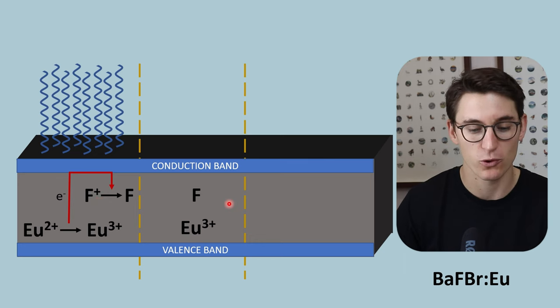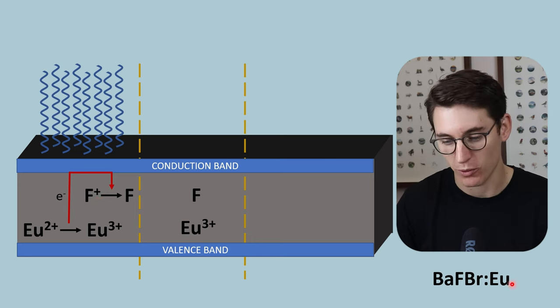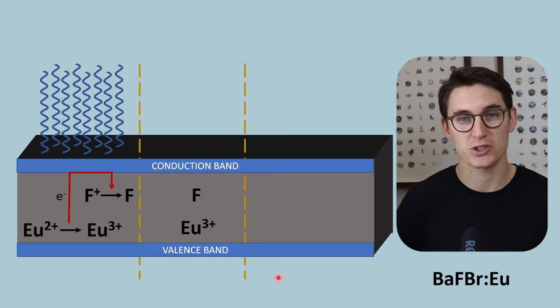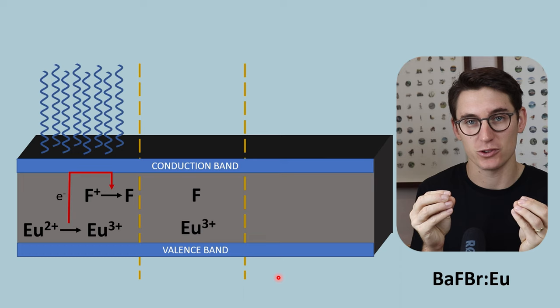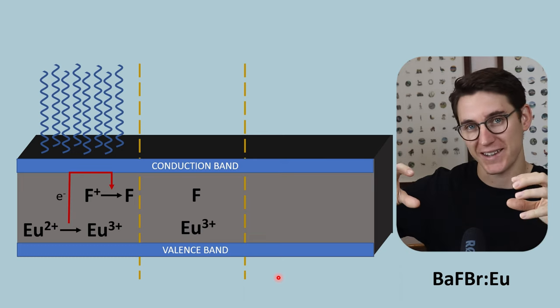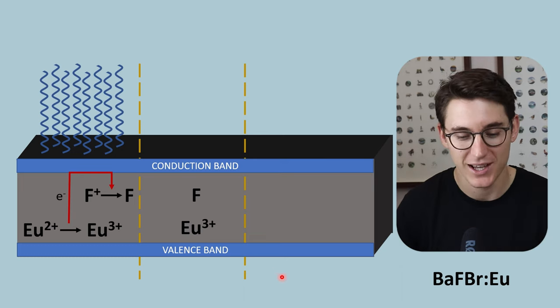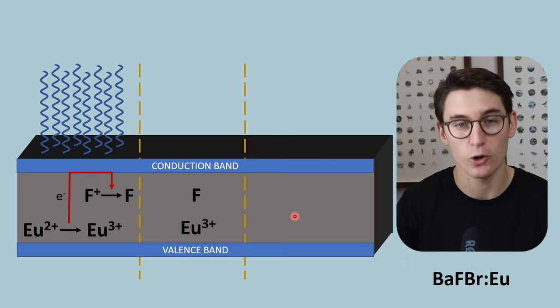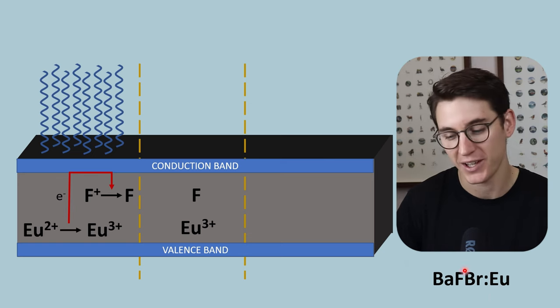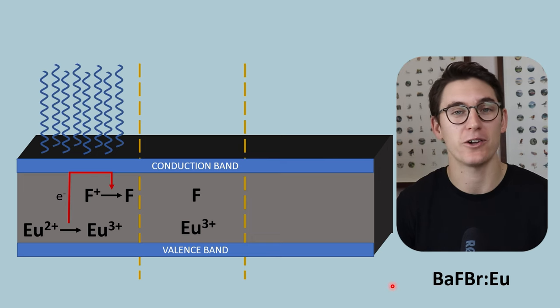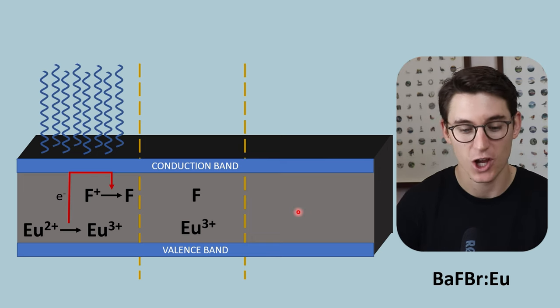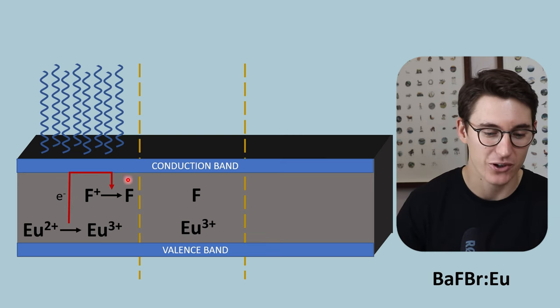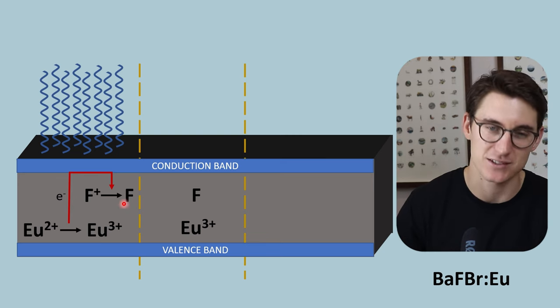The barium fluorobromide is doped by what is known as europium. When we looked at screen film radiographs, the silver halide crystals were doped by silver sulfide, which disrupted those crystals. The same thing happens here — when we introduce europium into the barium fluorobromide crystals we disrupt the structural integrity of those crystals and create what are known as F-centers.